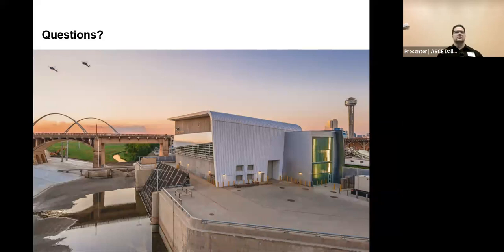During the pump test, the model test that you did on the pumps, did y'all try to predict how high the water column would be? We were putting people on each of the bridges during the testing, thinking that we were going to get overspray from the pump test, but it really didn't turn out to be a big issue. For the water column, we were hoping for a not-windy day to keep it straight up and down. As we said, it's a little bit higher pressure with the orifice plate. As you could see in one of the videos shown earlier, water was shooting out the pipe ends. So it was just a lot of pressure. We actually added those vents as an addendum, to relieve some of the pressure from the pumping going to drain. And that actually did help, especially during testing.